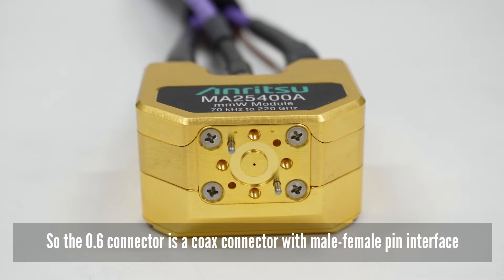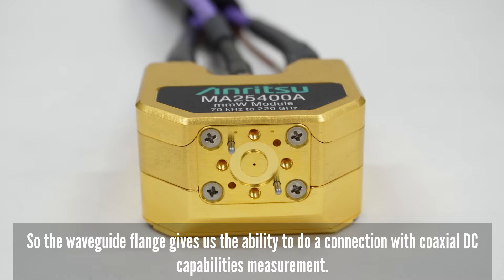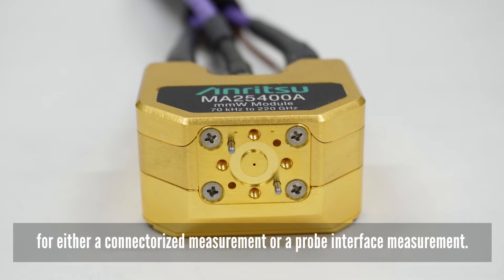The 0.6 connector is a coax connector with male-female pin interface. However, what we use is the UG387 waveguide flange. The waveguide flange then gives us the ability to do a connection with coaxial DC capabilities to do either a connectorized measurement or a probe interface measurement.